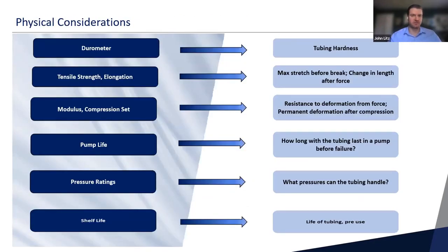What are some of the physical considerations for choosing the right tubing? One of the first things that you might think of when it comes to tubing is the tubing hardness, right? And that's represented by durometer. So the general measure for durometer is going to be what is called Shore A. There's also Shore D, which is generally used on more rigid tubing like a fluoropolymer. But Shore A is primarily what you're going to be seeing in the bioprocess industry. So when we say a tubing is a 50 durometer or 50 Shore A, that's going to be softer than something that's going to be an 80 Shore A durometer.